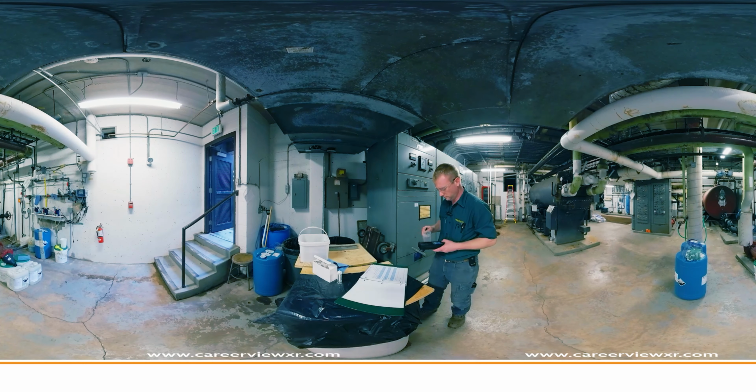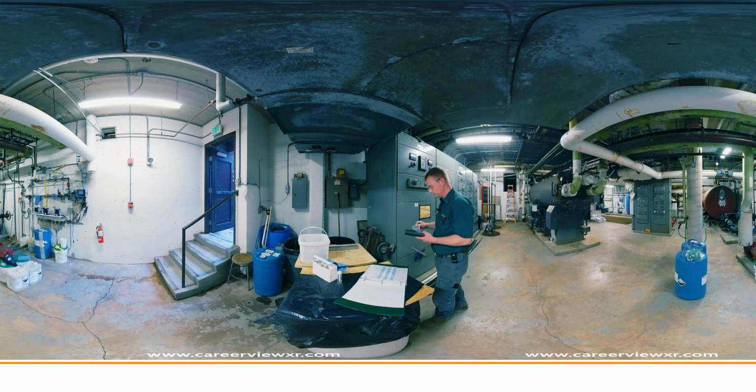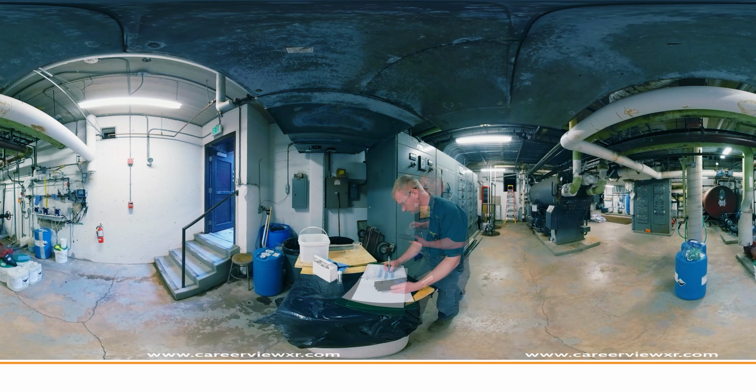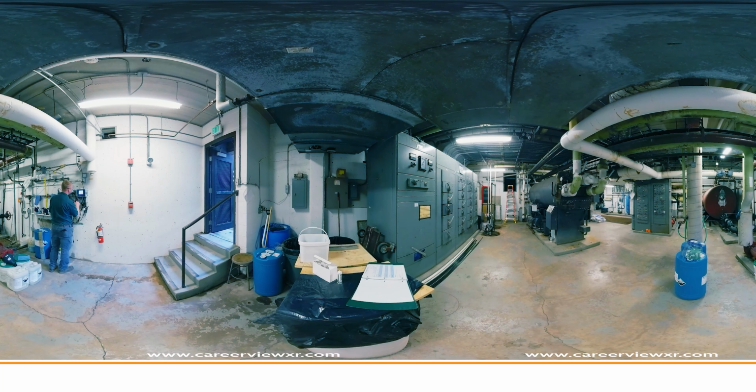Cooling towers are monitored by routine water testing. Eric is testing the cooling tower water for conductivity, PTSA, and bacterial growth. He documents the results. Eric verifies that the controller reading is accurate and can calibrate the chemical feed system if needed. Regular testing helps to determine if treatment is working properly.